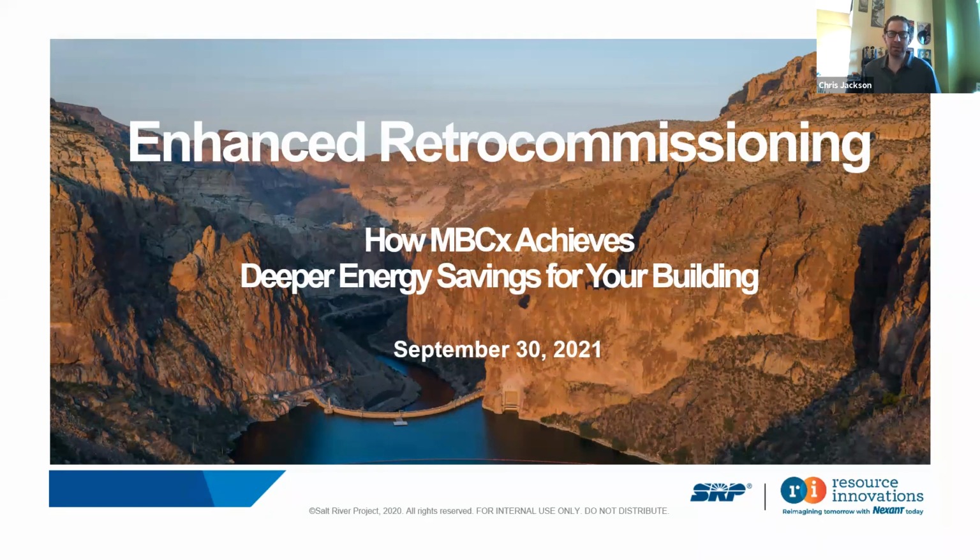Even if you don't have those amounts, you can proceed with retrocommissioning and monitoring-based commissioning outside of the program. If you don't qualify, you'd miss out on some assistance from SRP. But the key is that a chiller plant is a nice boost. It usually means you're a higher power user. If you have a building automation system, it's a lot easier to connect up a monitoring-based commissioning platform, even if you have heat pumps or rooftop units, something that you can see digitally in a BAS. But even if you don't have a digital BAS, there are ways that you could deploy remote monitoring. It may require some sensor installations and even some cell modems that send the data up to a cloud. So even if you don't have a BAS, there are ways that you can qualify. It just increases the installation effort and cost a little bit.